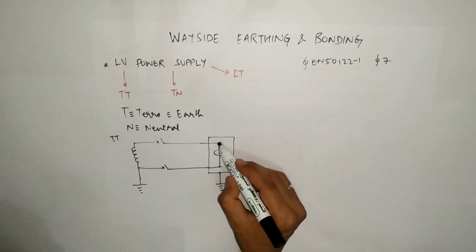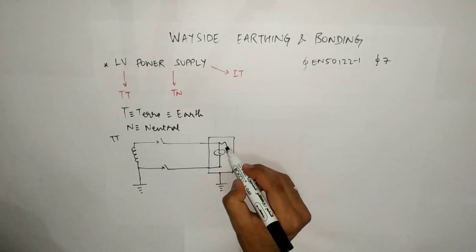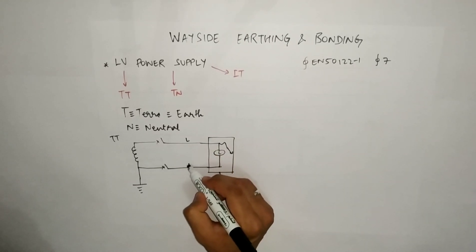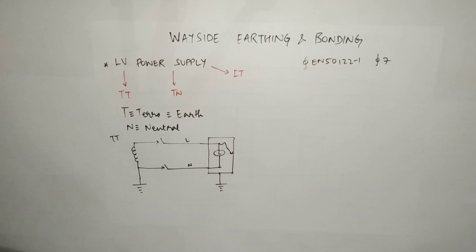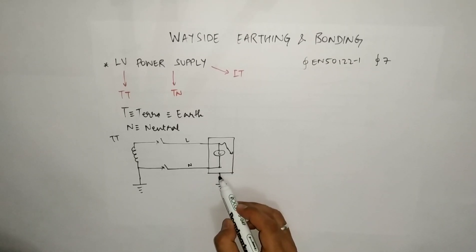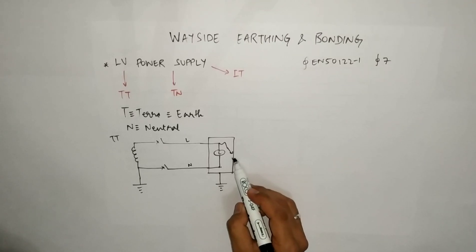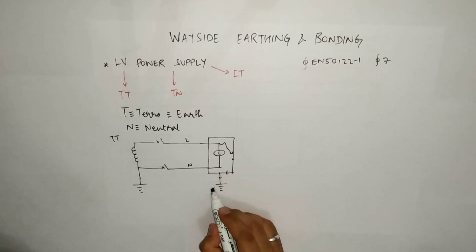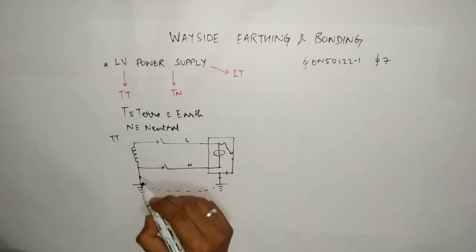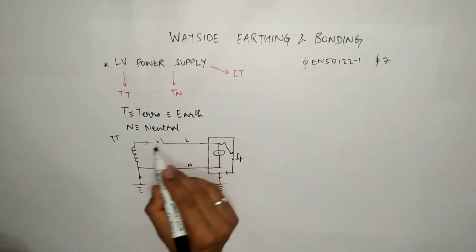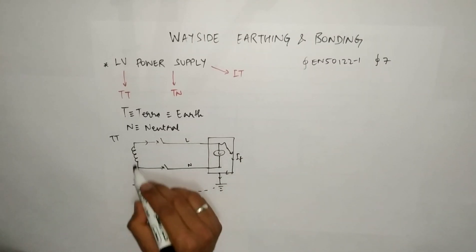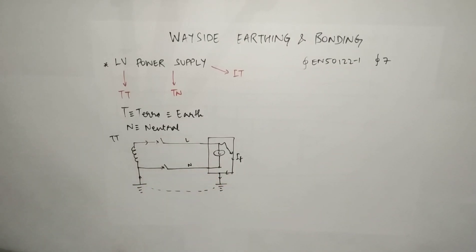In case there is a fault — suppose the line conductor is touching the enclosure. Since the equipment is connected to earth, the current will start flowing and go back to its source, completing the path. The fault current will flow through the body and then through the earth, leading to the tripping of the circuit breaker.